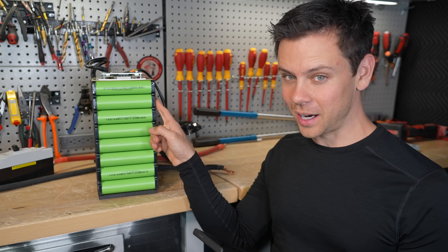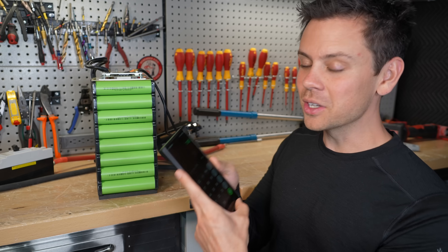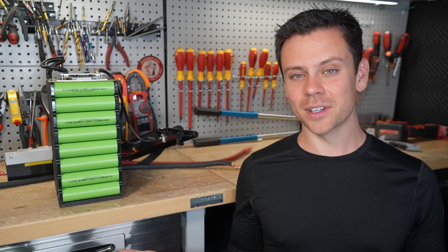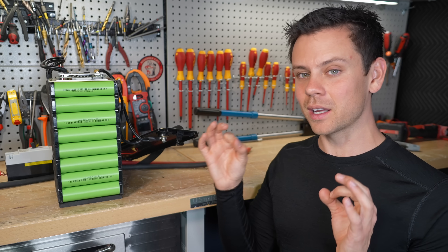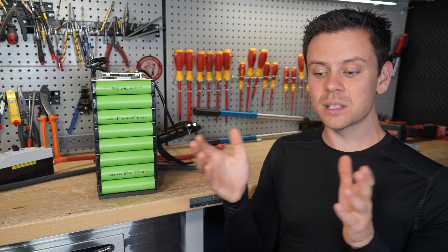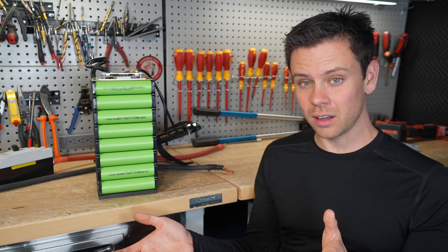If you have a 48 volt battery with a 12,000 watt inverter and divide by 48 volts, you get 250 amps. Copper is not free, so you need to buy larger cables, and not only are the cables going to be a lot larger, but you need to make the BMS and the breakers much larger as well.